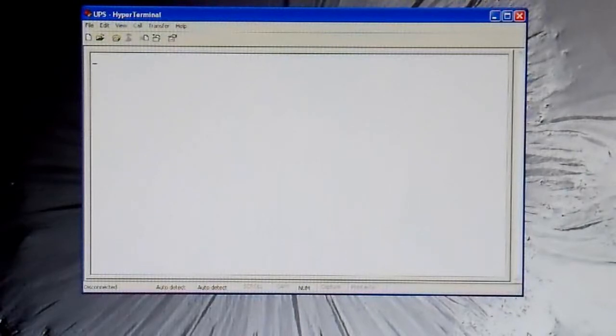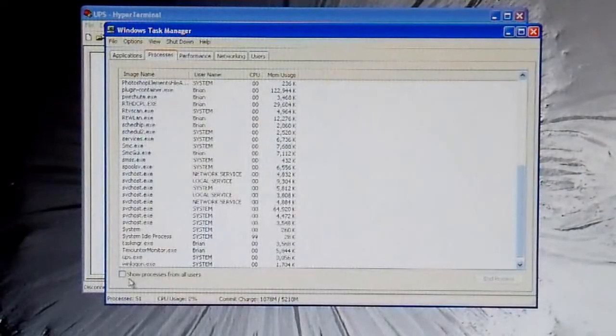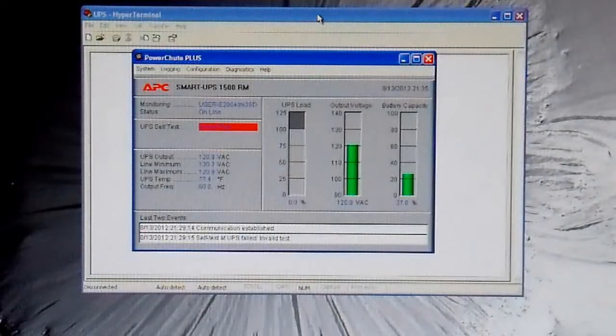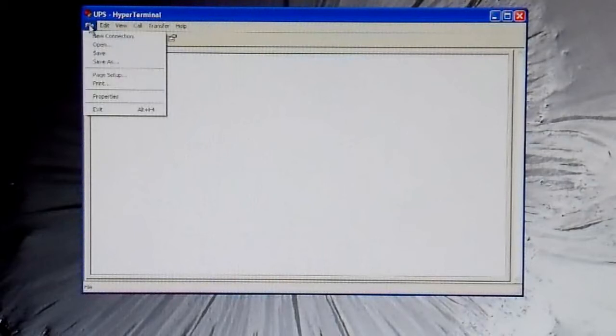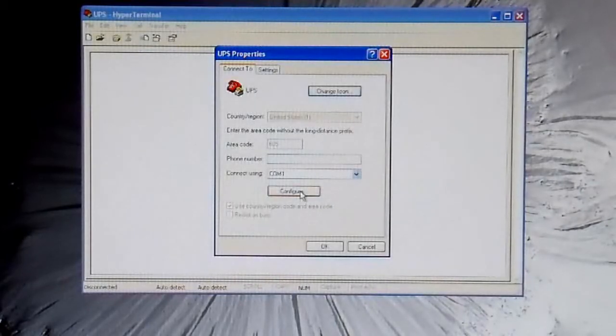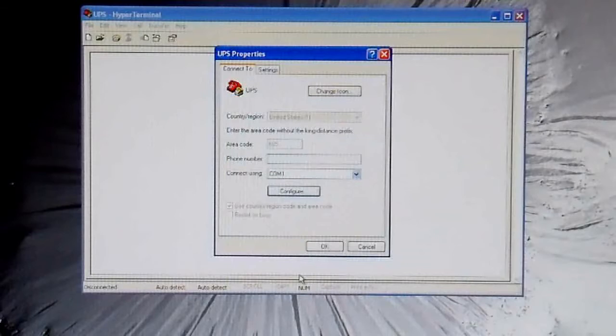In order to use HyperTerminal I first have to disconnect from PowerChute. I'll open up Task Manager and end the UPS service — that will free up the COM port. Your computer may be different. Now we're ready to connect. Going to properties: COM1 is what I have it connected to. To communicate with these using the smart protocol, use 2400 baud, 8 data bits, no parity, 1 stop bit, and no flow control — so 2400, 8N1. Connect.